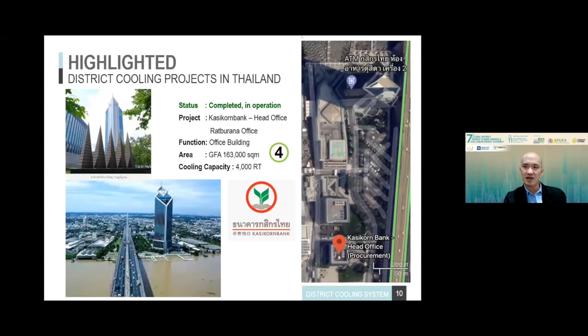So number 1 to number 4 are existing and operating district cooling systems in Thailand. Number 5 is being developed or under construction: the Forestry, a mixed-use development including residential condominiums, service apartments, detached houses, and commercial development including hospital, office, hotel, and community centers. They design it so they use district cooling with underground piping, and they don't have air conditioning condensing units, even in the residential area.